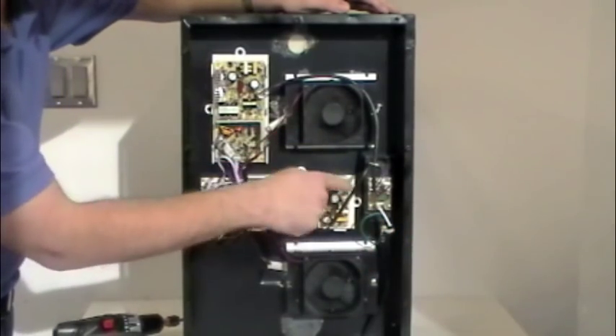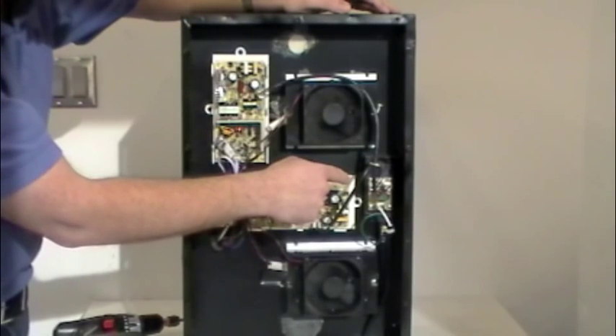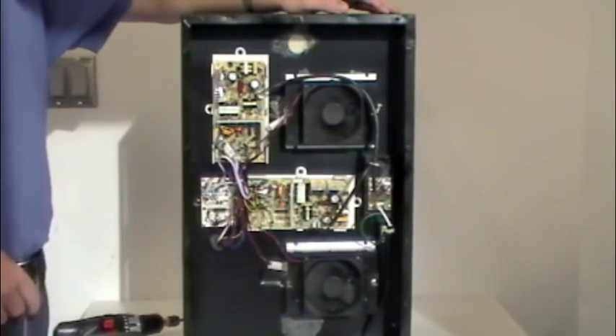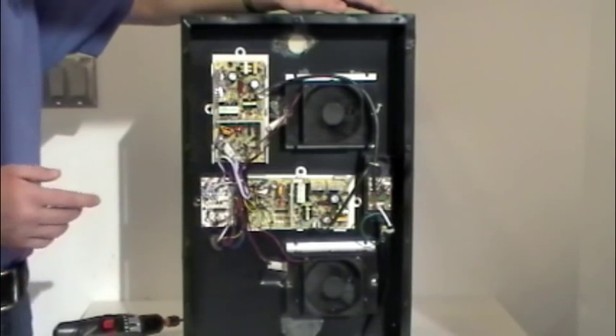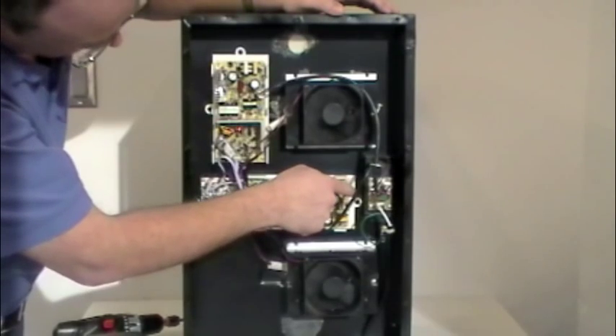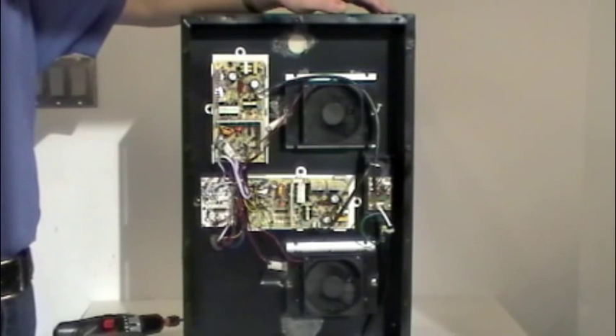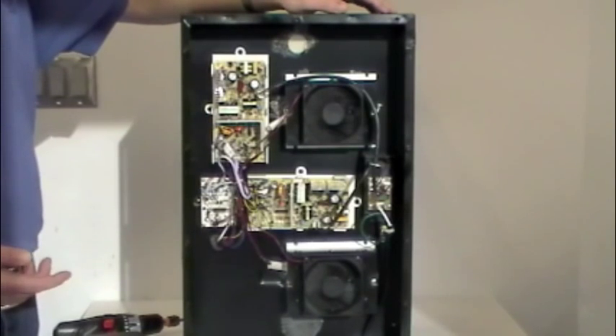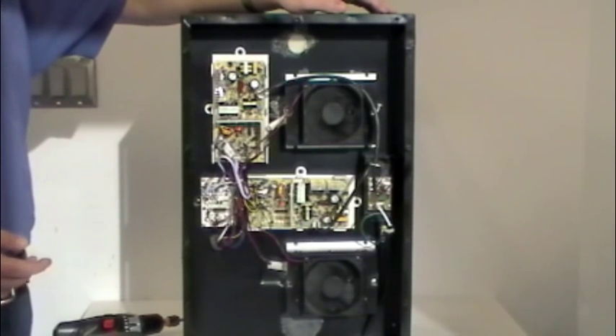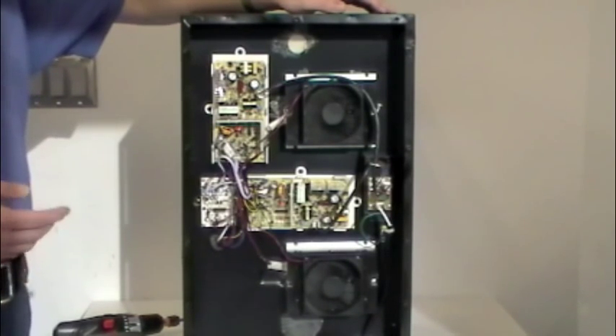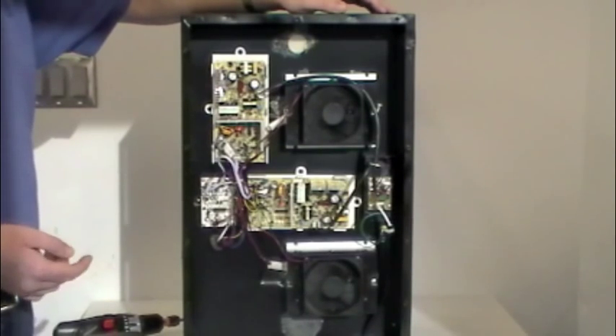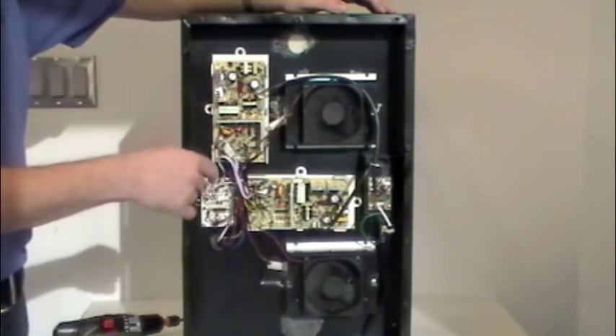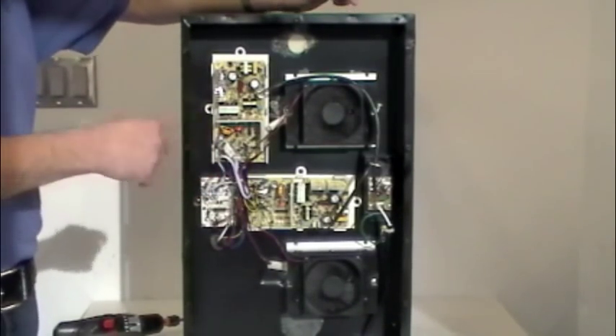First thing we're going to talk about is power input. We do have a filter board here. We have a choke coil here in the center. You can see that copper colored coil there wrapped with the green tape. That's to prevent RFI interference. We also have on the board here underneath and next to that coil some MOVs, metal oxide varistors. That helps in the surge. Obviously the varistor will absorb so much energy and then it will fail. The good thing about it though is that when that spike hits, the board will absorb that energy. We're not going to transmit it over here to the circuit board.